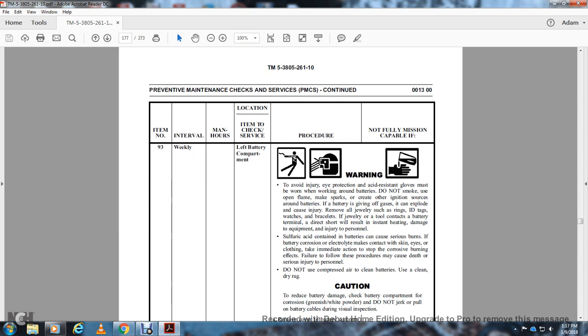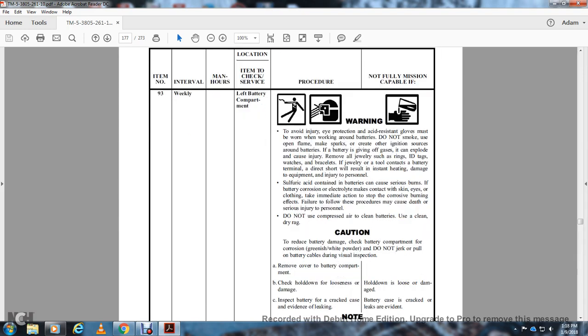Remove all jewelry, such as rings, ID tags, watches and bracelets. If jewelry contacts the battery terminal, a direct short can result in instant heating, damage to the equipment and injury to personnel. Sulfuric acid contained in the batteries can cause severe burns. Battery corrosion electrolyte can contact skin, eyes and clothing. Take immediate action to stop the corrosive burning effect. Failure to follow these procedures could cause death or serious injury to personnel.